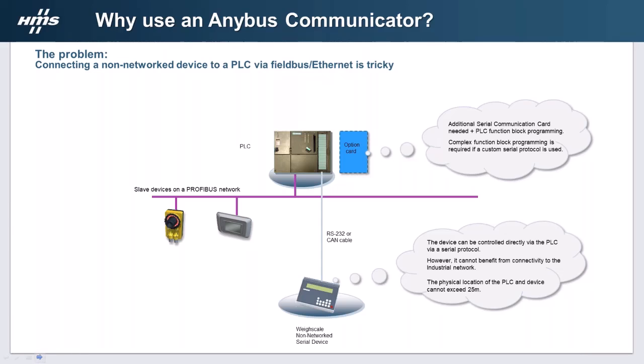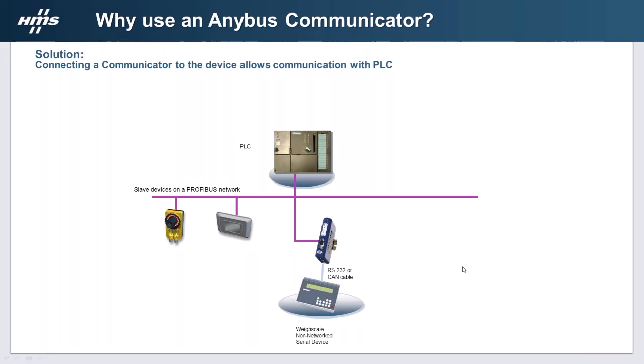So another option — drumroll please — is the Communicator. All it does is take the serial output from that weigh scale and convert it to Profibus so it can sit on the network. As far as the rest of the network is concerned, that weigh scale is on the network — they don't realize there's anything in between; it just looks like it's on the network. So if we go back to that factory owner with a tried-and-tested barcode reader in the corner, all he has to do is add one of these devices for about £400, a few hours of configuration at most, and suddenly he's got that machine up and running again.